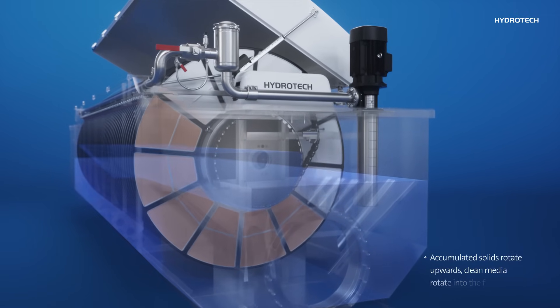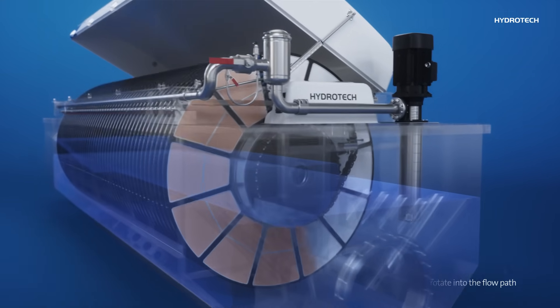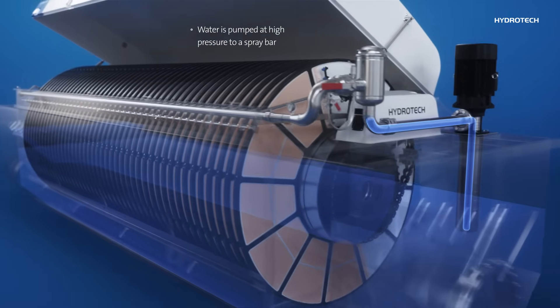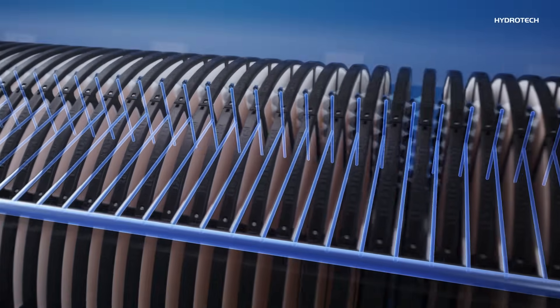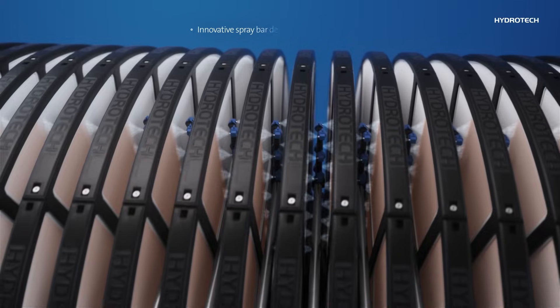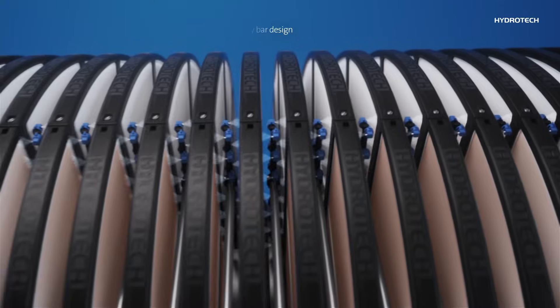Accumulated solids rotate upwards and clean media is rotated into the flow path. While the discs rotate, a small portion of treated water is pumped at high pressure to a spray bar with nozzles. The spray bar is a patented design by Hydrotech. It reduces the amount of water and power required for the backwash.